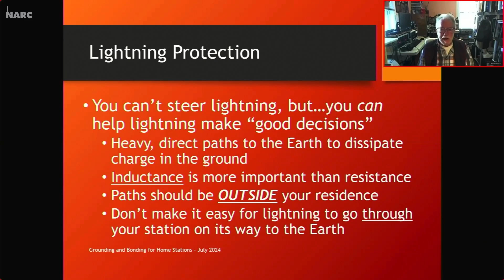All of these low inductance, heavy direct paths should be outside your residence. Do not invite lightning into your house. If you have an earth connection, a lightning protection system, it should be outside the residence. Don't run lightning protection conductors through your attic, crawl space, or basement underneath the living area. Just don't do it if you can at all avoid it. Don't make it easy for lightning to go through your station on its way to the earth. All these protective paths should be outside.